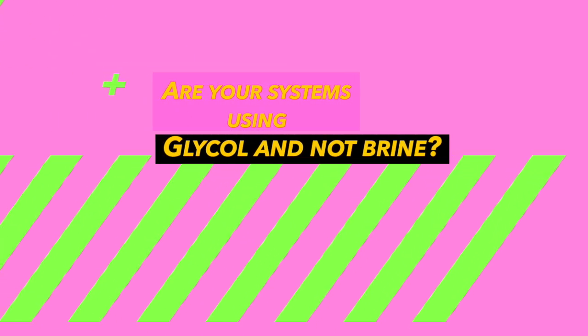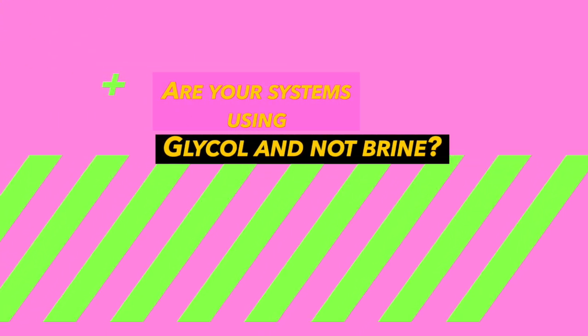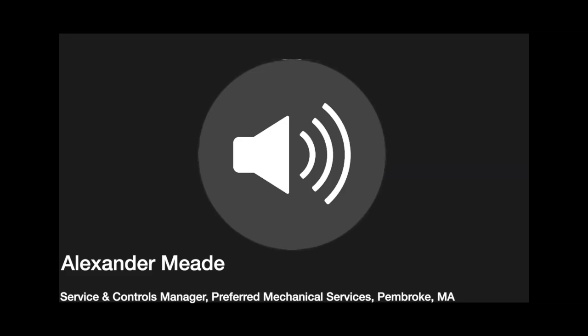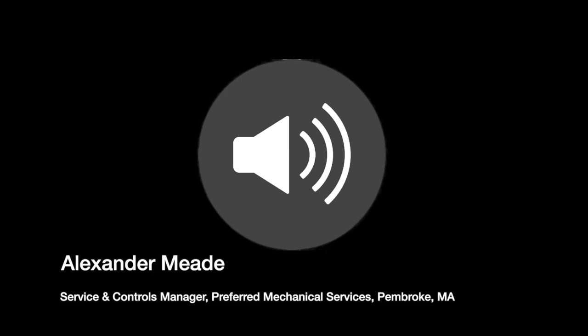Your systems are typically using glycol and not brine, is that right? Both. Yeah, I would say it's probably 70% glycol, 30% brine. He's talking about with the sensors in the floor. I do have those in the floor. Right. And the system shuts off 6 degrees colder than the set point. Yep. Yeah, it's typically between 3 and 8 degrees below your active slab set point is where you want to run your glycol.